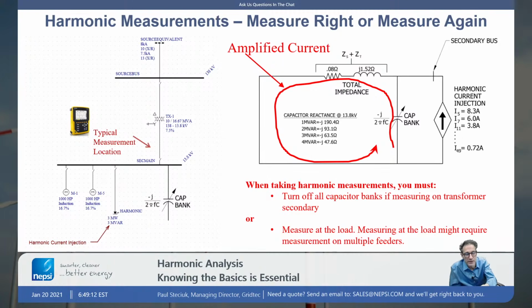And also, I didn't say it, but these values of current here have phase angles. Each and every nonlinear load will produce a certain amount of harmonic current. That harmonic current has a phase angle associated with it, so those currents don't necessarily add. So taking measurements at this location here is nice because it allows you to capture the summation of the entire plant. What's important is that the capacitor be removed. The capacitor has to be disconnected. 15 minutes with the capacitor disconnected is better than any other measurement you could have. So you ask the plant operator to take the capacitor banks off so you can obtain the proper value of current at that location.